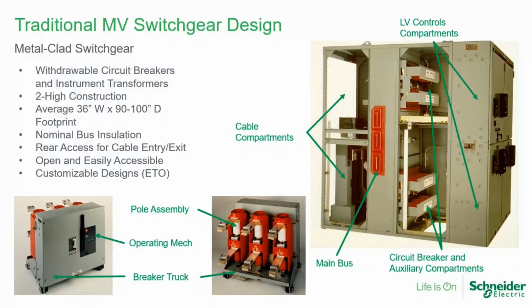Generally, two high construction breakers on the top or the bottom. This can be limited a lot by the current ratings, the heat dissipation requirements, and a lot of times the voltage ratings can limit between 1 high and 2 high. But generally, in applications at 5 and 15, and often at 27 kV, you can do 2 high construction. At 38 kV, I think all the manufacturers that I've seen have been limited to 1 high construction. We average about a 36-inch wide by 90 to 100-inch depth and footprint.